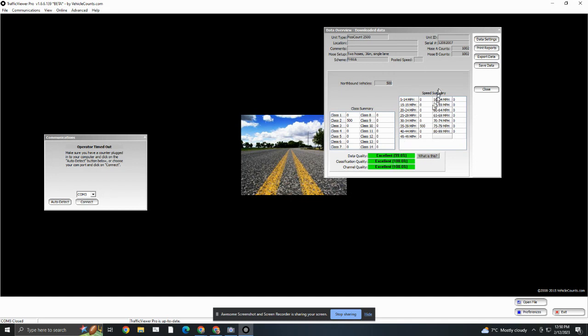If they're in 100%, which they are, 100% and 100%, they're 100% in agreement. If they're out of balance, that percentage will reflect the amount of out of balance they are, which usually, if it gets pretty far out, is an indication of something wrong with one of the hoses. Not absolutely certain, but 99% of the time it's a problem with the hoses.